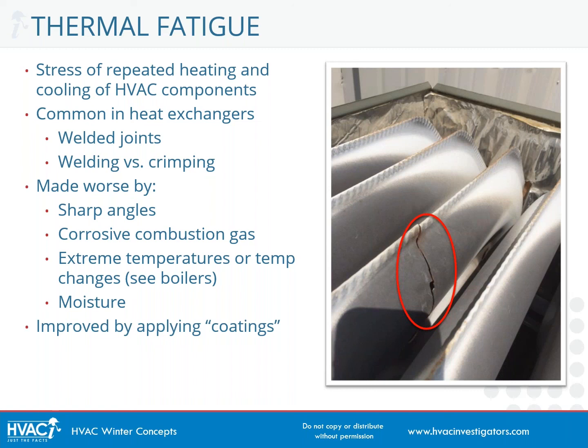Because of all of these issues, manufacturers have gotten smarter about the way they construct heat exchangers. They've started to both apply coatings to the heat exchanger and sometimes use special alloys to prolong their life. It does slow down these effects by a number of years, but no matter what we do, it's still going to rear its ugly head at some point. If you own and use the system long enough, the heat exchanger will fail.